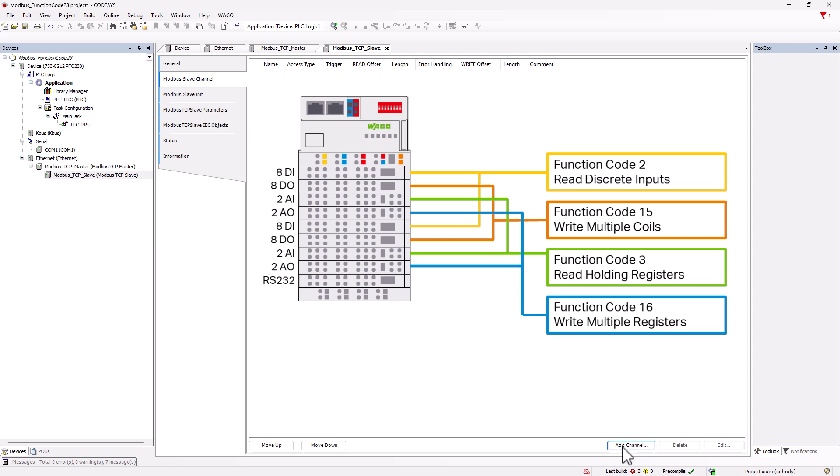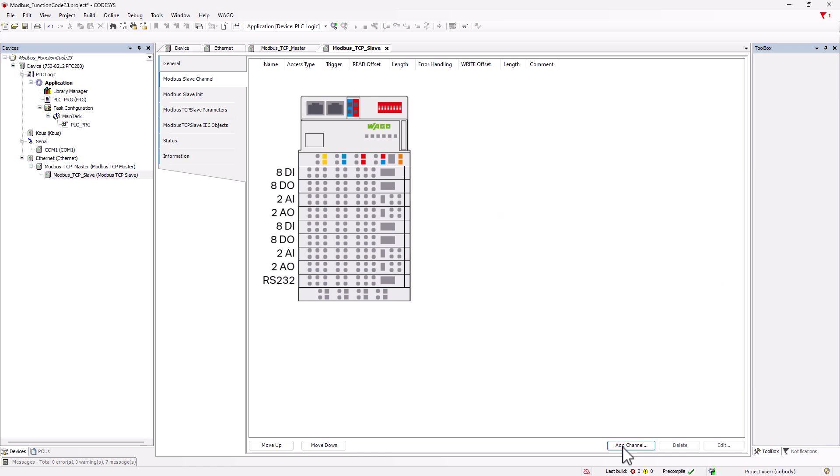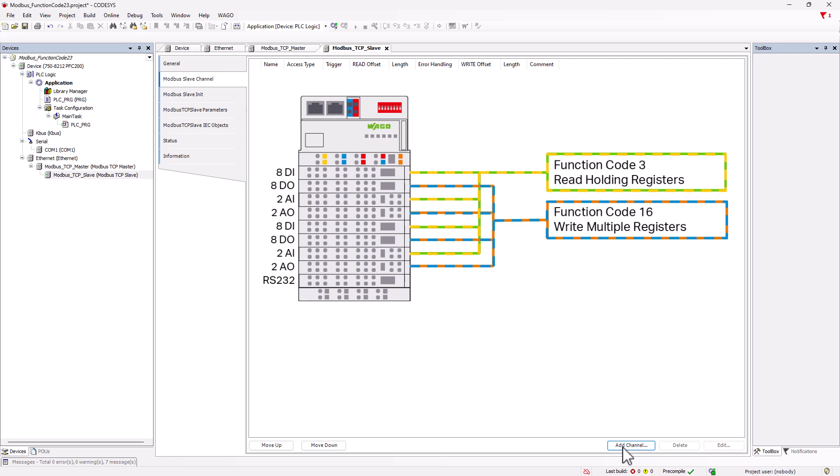The complex module, the serial interface, could then be captured with function code 23, and all inputs and outputs would be recorded in five channels. Alternatively, you could group all inputs with function code 3, and all outputs with function code 16. The serial interfaces would then remain at function code 23. This would almost half the number of bus queries and create a significantly more performance system.